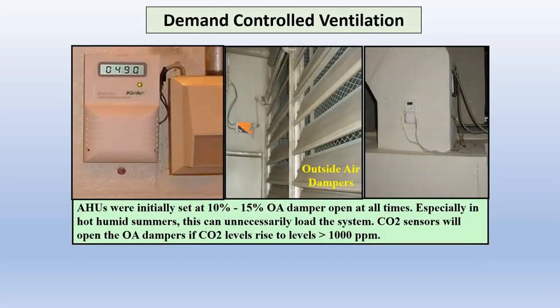So if I'm going to do demand control ventilation, in this particular situation, these are set at 10 to 15% open at all times. Not uncommon when you're out there in the field, you see this a lot. Really not good, especially if you have a lot of humidity. You're pumping in air you don't need. The CO2 sensors, you see one on your left there, will open the outside air dampers. Those are in the middle. You can see the actuator here. And the way I set them up was they start opening when the CO2 levels rise to greater than 1,000 parts per million, or they start opening a little bit more.